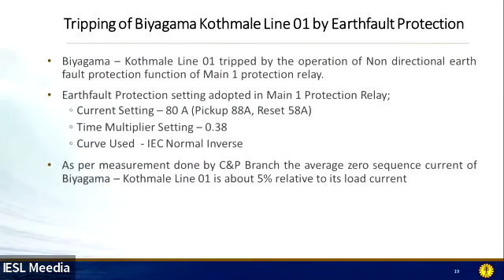But after the total failure, we went to almost all the important lines and measured the zero sequence current. In this particular Biyagama-Kothmale line 1, it was found that the unbalanced current is about 5% of the load current. So when the current goes up to about 1,500 amperes, we get around 75 amperes of unbalanced current.